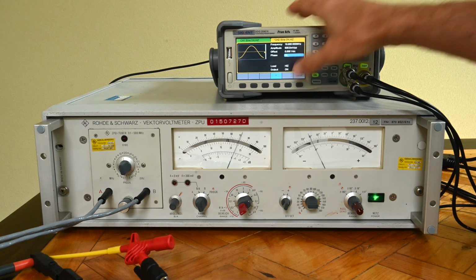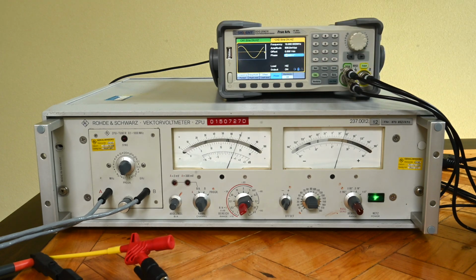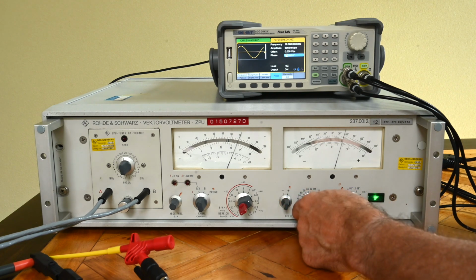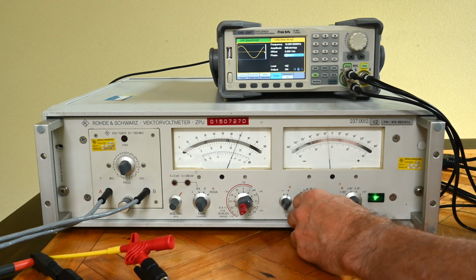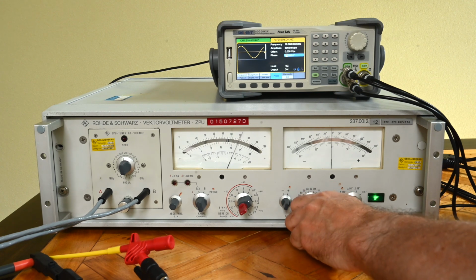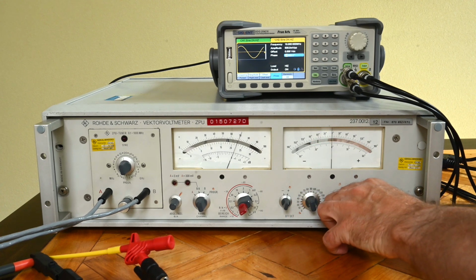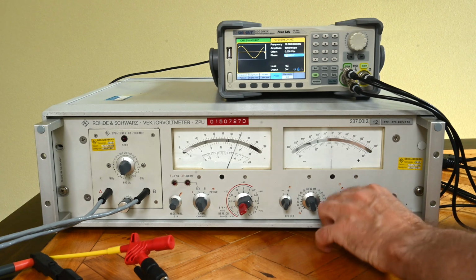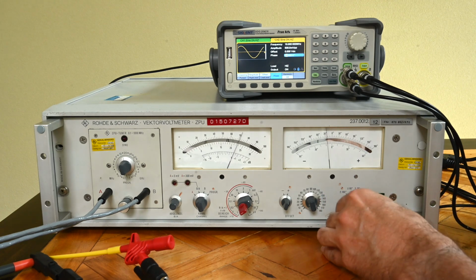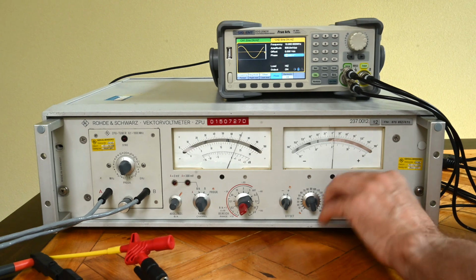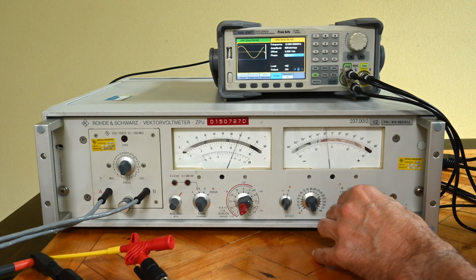To do that, I'm going to go to a positive phase of 50. And now I want to try to measure a phase difference relative to the 50. So I would start to calibrate that. There's actually a calibration possibility here in 10 degree steps. So let me put this more or less at about 5 steps, because I'm looking at 50 degrees. Now I'm going to go to a more sensitive scale, plus minus 60, plus minus 18, and I can use this little adjustment over here. I can even go to just 6 degrees. It's going to be super, super sensitive here.